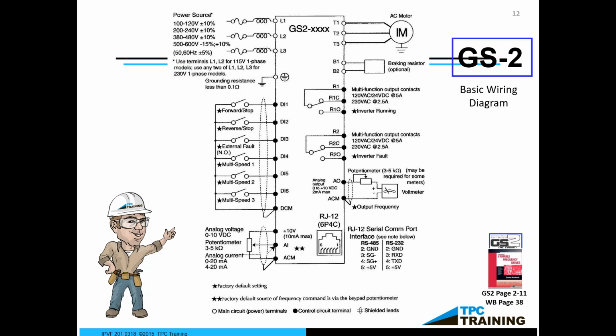Having said that, this particular drive and all the other drives you can tie to your PLC system too. Programmable logic controller. So you can get your digital inputs either from a switch or a PLC, or you can use your relay outputs and tie them to the PLC. So these are very interchangeable. Whether it's digital outputs, analog outputs, digital inputs, or analog inputs, they can tie right to your SCADA system or your energy management system.